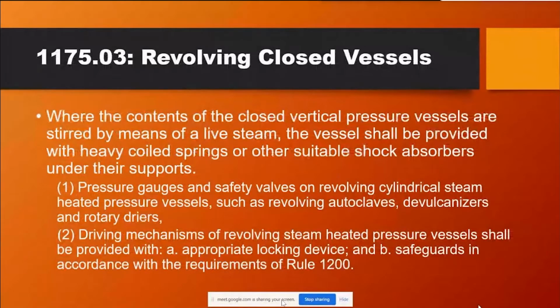Revolving closed vessels, where the contents of the closed vertical pressure vessels are stirred by means of a live steam. The vessel shall be provided with heavy coiled springs or other suitable shock absorbers under their supports. Pressure gauges and safety valves on the revolving cylindrical steam heated pressure vessels such as revolving autoclaves, devulcanizers, and rotary dryers. Driving mechanisms of revolving steam heated pressure vessels shall be provided with appropriate locking device and safeguards in accordance with the requirements of Rule 1200.